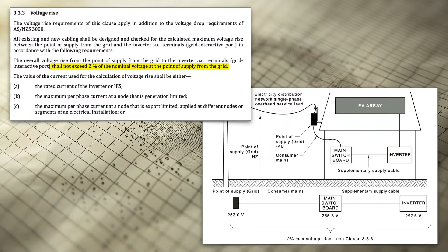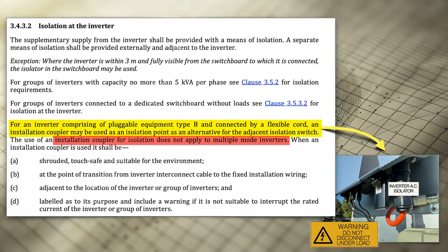All right, so this is about isolation of the inverter. So for an inverter comprising pluggable equipment, so this is coming back to that picture I showed earlier on, where you've got an AC plug that connects to the inverter that is of type B, i.e. requires a tool to disconnect, and it's connected by a flexible cord, an installation coupler may be used as the isolation point as an alternative to an adjacent isolating switch.